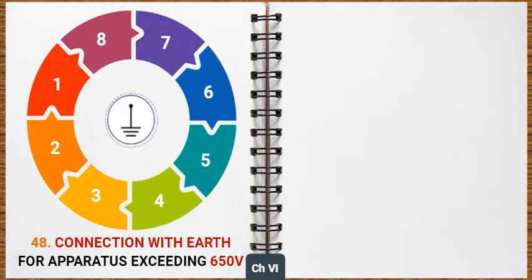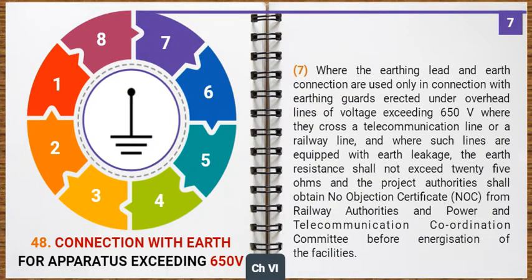Where the earthing, lead and earth connection are used only in connection with earthing guards erected under overhead lines of voltage exceeding 650 volt, where they cross a telecommunication line or a railway line, and where such lines are equipped with earth leakage, the earth resistance shall not exceed 25 ohms, and the project authorities shall obtain No Objection Certificate (NOC) from railway authorities and Power and Telecommunication Co-ordination Committee before energization of the facilities.